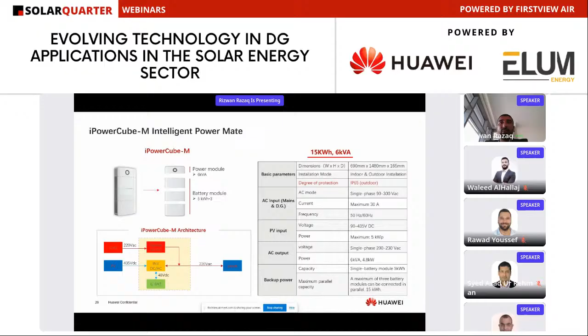So here is a clearer example with a breakdown of the calculations on the right-hand side. As I said, the power module is your top device in a modular unit, and then you've got 3 times 5 kilowatt hour units. Now, it doesn't come as one complete package. If a customer requires 5 kilowatt hours only of batteries, that can also be supplied, or alternatively, we can daisy chain multiple of these up, with a maximum of 3 into one power module of 6 kVA. On the right-hand side is a breakdown of the power capacity from the PV side, and from the AC power output. Typically, this is provided for single-phase applications, which is quite common for the residential projects themselves.